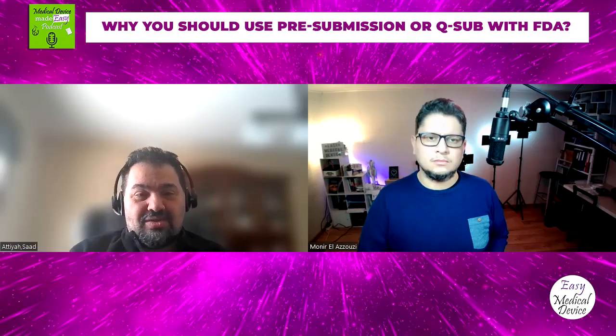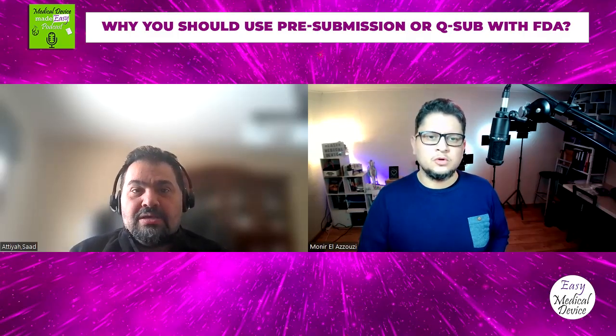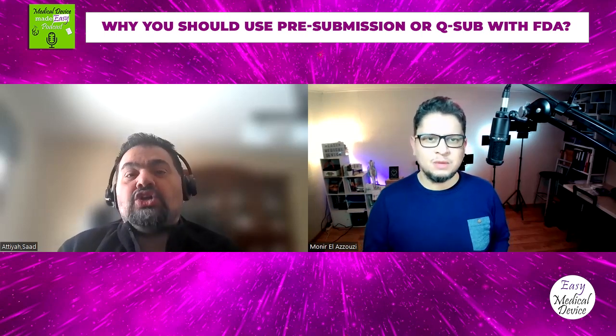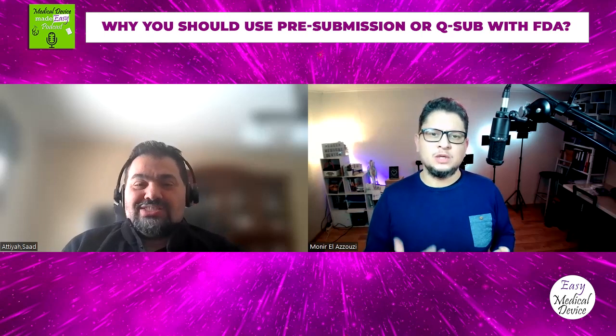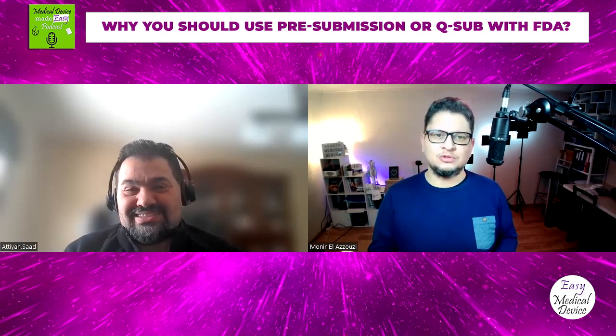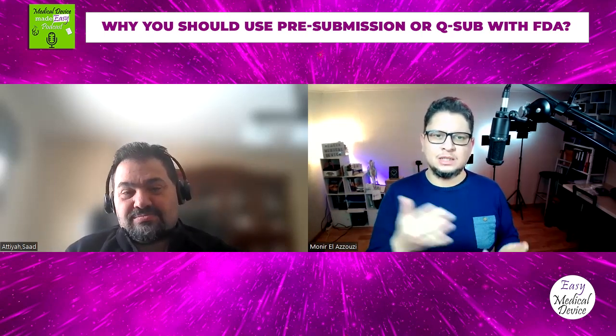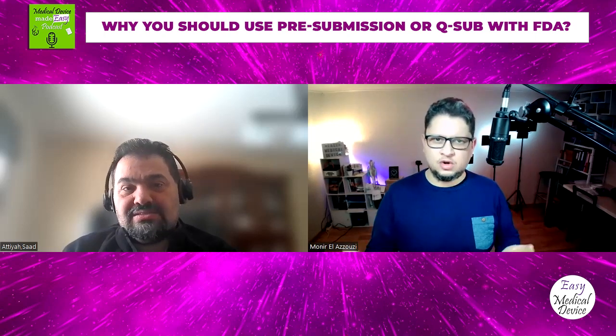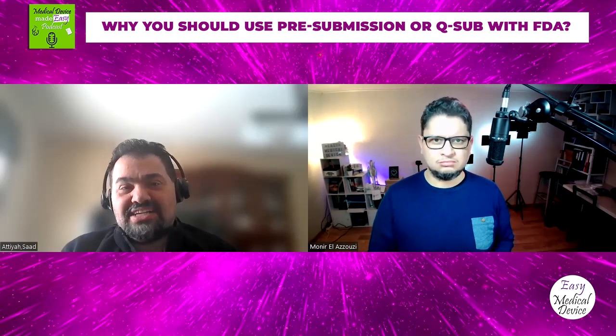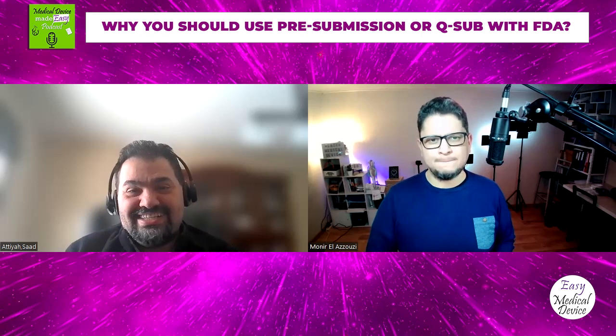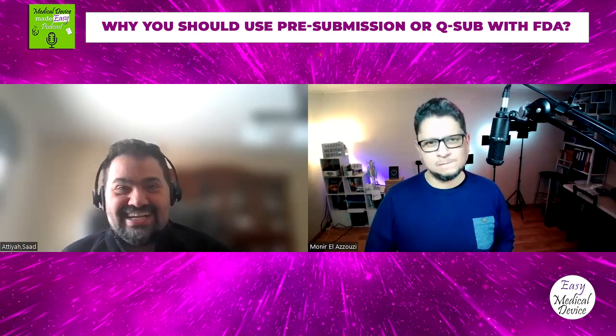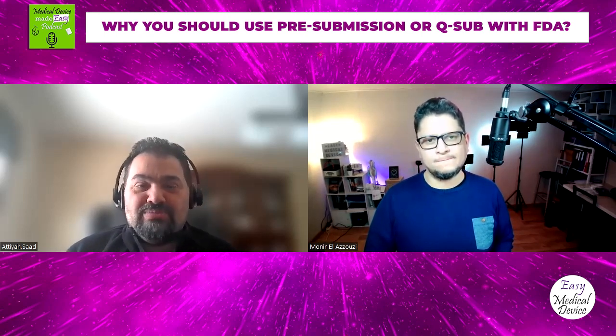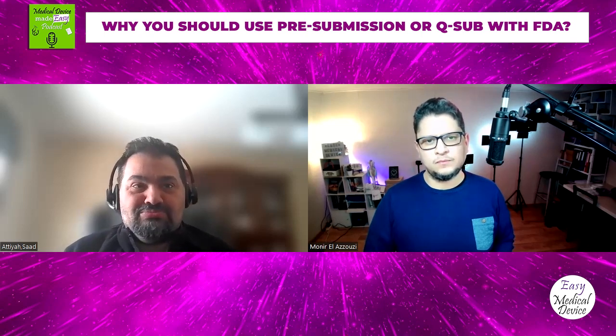questions with FDA. So questions, as we say, is not like, what is the classification of my product? Questions is, here is, I think, the classification of my product. Here is, I think, the predicate. Here are the elements. Do you think it's correct? Is it like that? So something to that effect. There are good questions and there are bad questions. And we can go over the good and bad questions a little bit later.